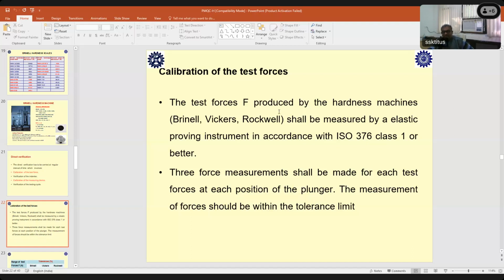You have to put the load cell, and you have to measure the force, rotating the load cells at three different positions. And also, because sometimes the block height, the block thickness are all different, you can measure the force even at three different heights also. So that will give you a very good idea whether the machine is applying the required force as specified in the standard with the tolerance mentioned in the standard. So that we have to ensure by calibrating the force independently.